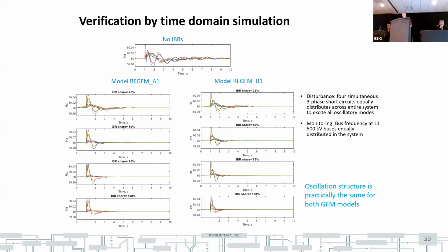And that slide shows confirmation in time domain of the same results. On the top, that is a picture of transient when you don't have inverters. On the left side, one model, and on the other side, another model. From the top to down, it's 25, 50, 75, and 100% inverter penetration. And those results confirm small signal analysis, showing that if you increase the number of inverters, then damping is increasing and oscillation practically disappears. And again, it's an extremely positive result.